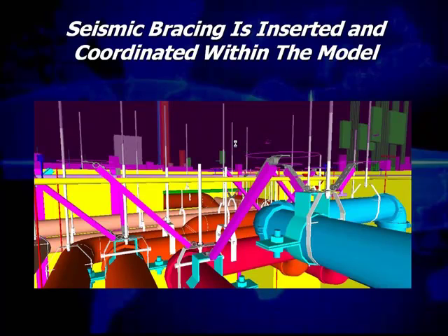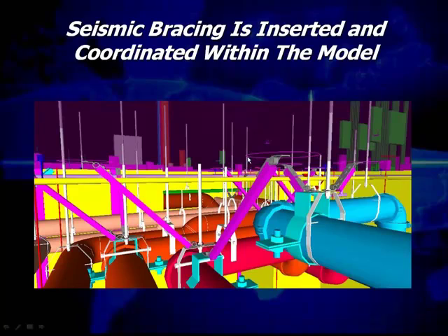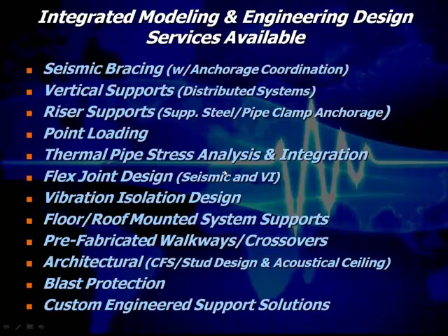But at a minimum, we can do the brace arms and also show, if you're not familiar with it, this halo shown at the top of the brace arm is the actual anchor spacing required to remain clear of other adjacent anchors, so that the anchor remains valid from an engineering standpoint. Very common in the state of California. I'll talk about that more in a little bit.